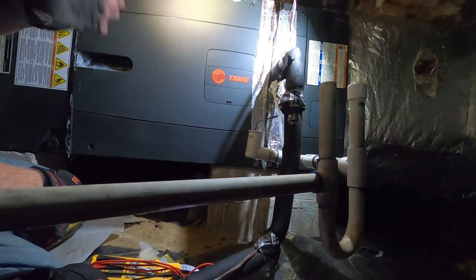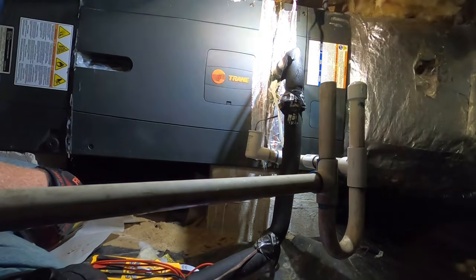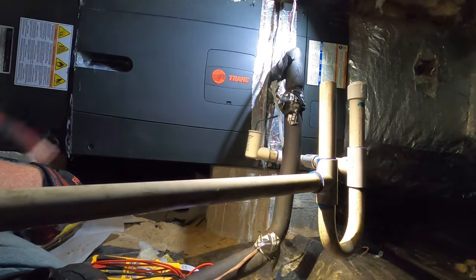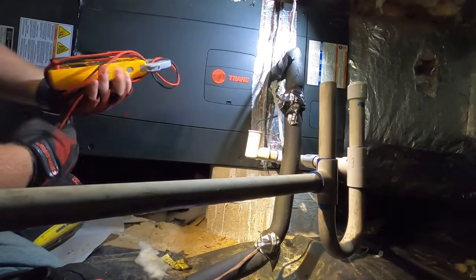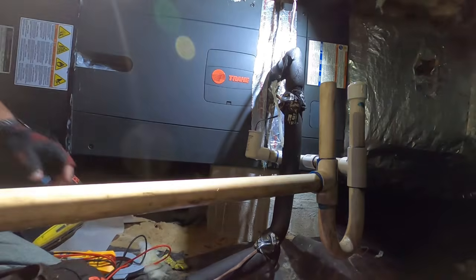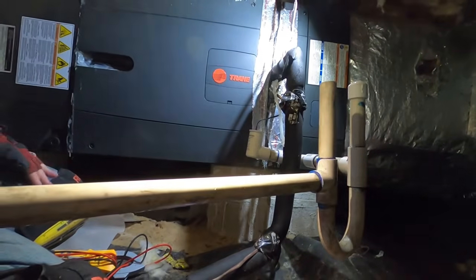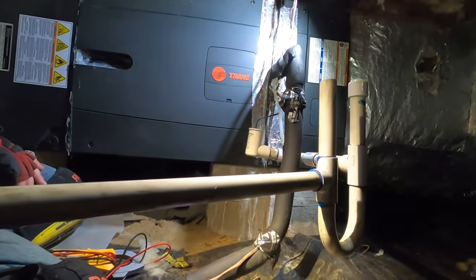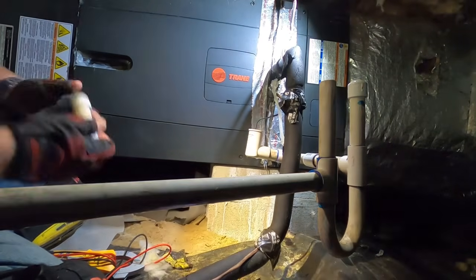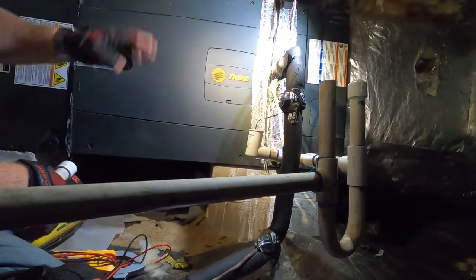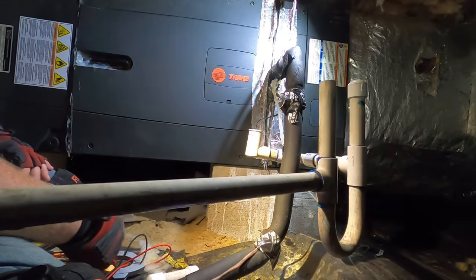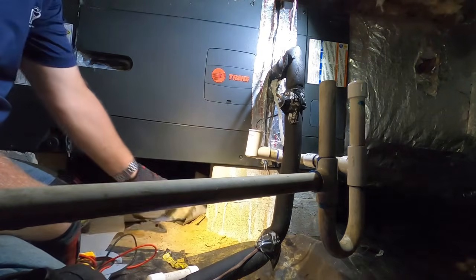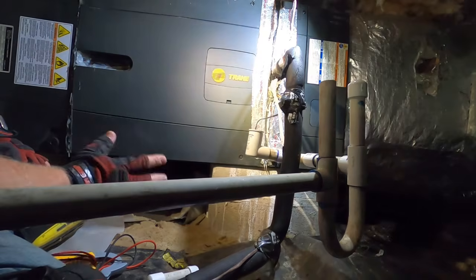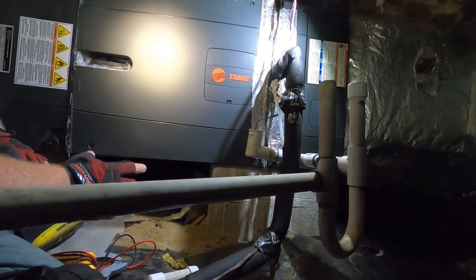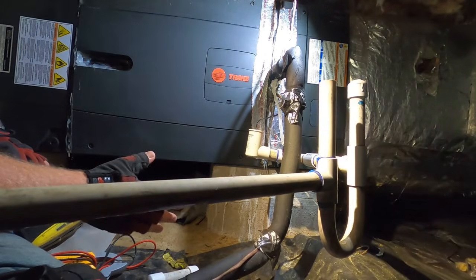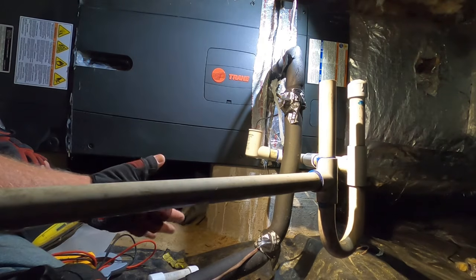So now we're under the house, and I've got the outdoor disconnect turned off. I'm letting this blower run. I want the temperatures on this coil to stabilize with the airflow so I can test my temperature sensors, and then we'll go over and check that stepper motor in here. And as long as those things check out okay, I'm comfortable with the diagnosis of the EEV board.